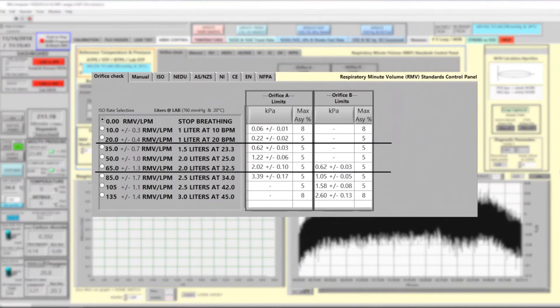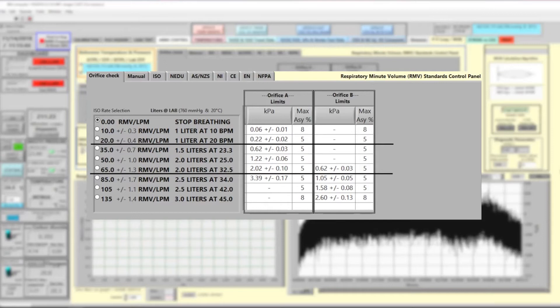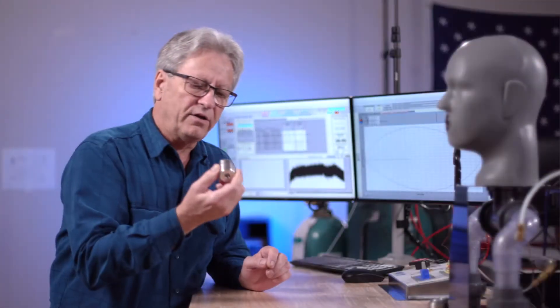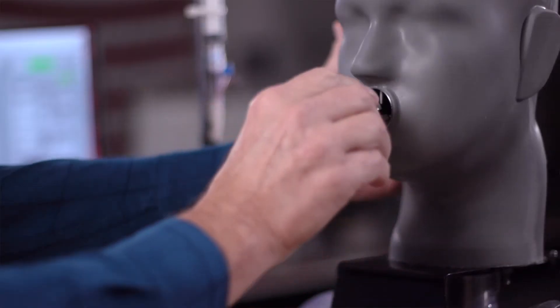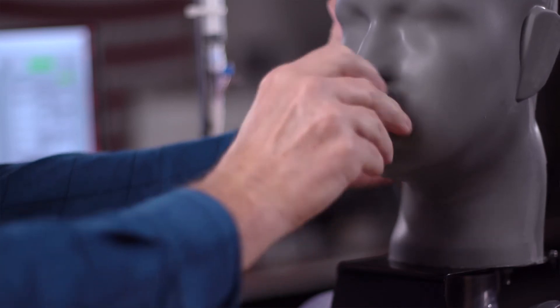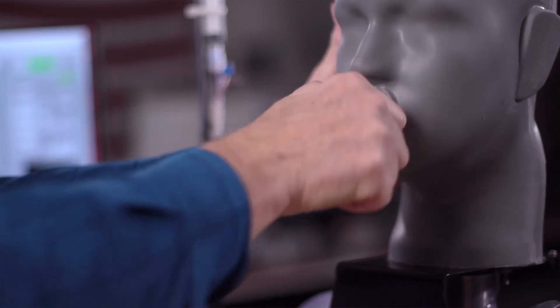Here, the ISO verification orifice numbers are laid out in a table and we'll take orifice A and use it for an analysis on one of the verification parameters.